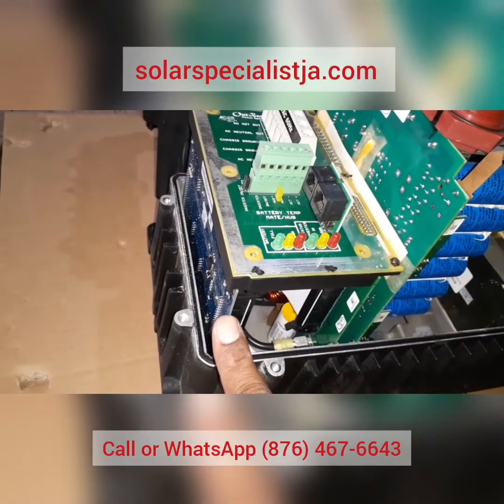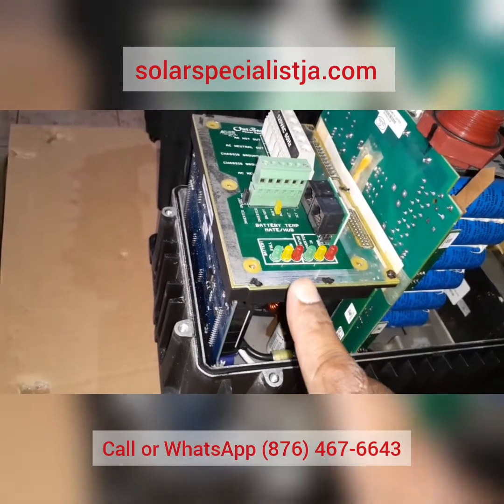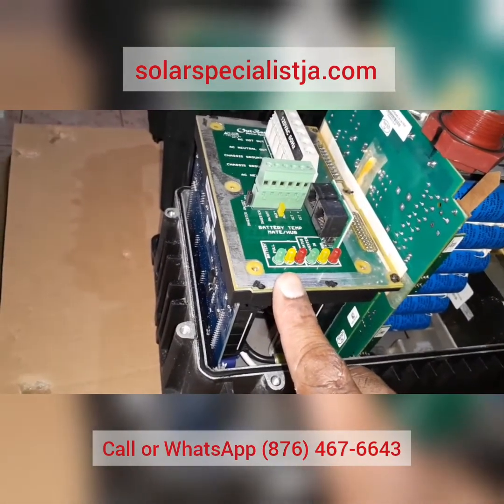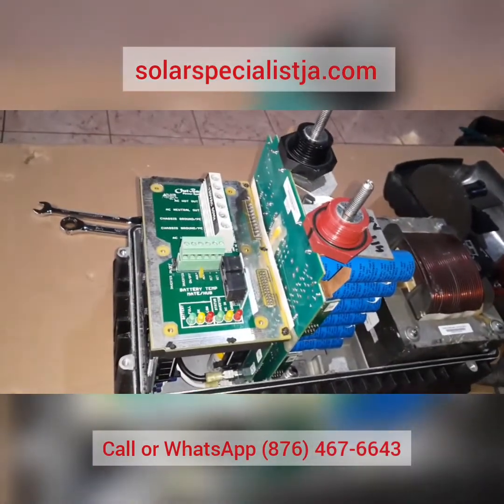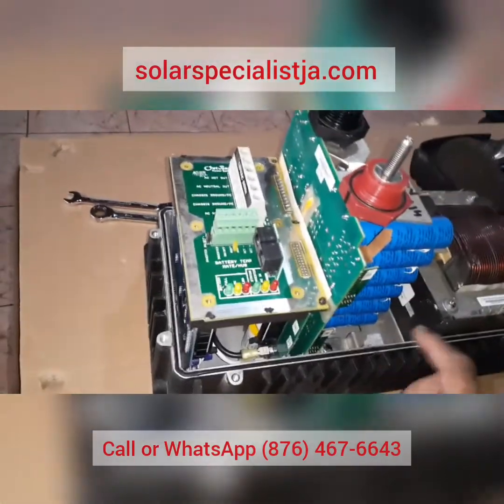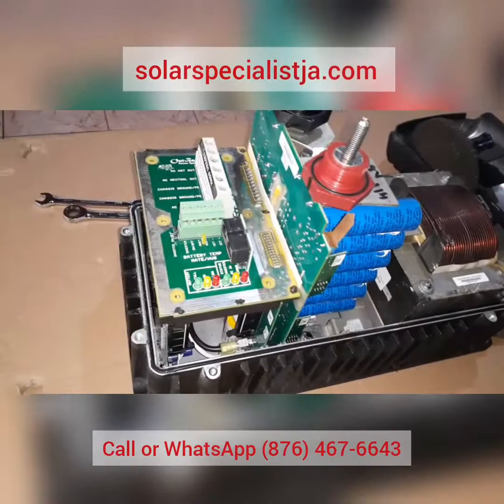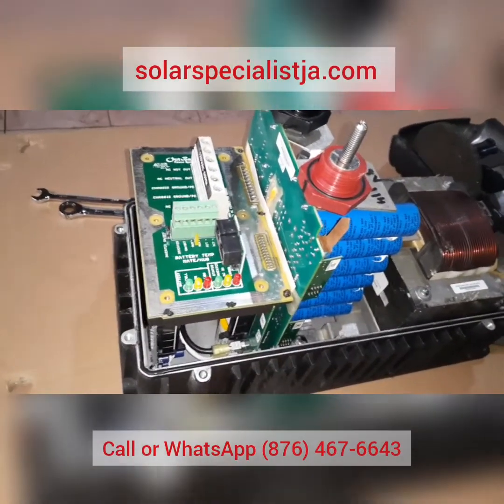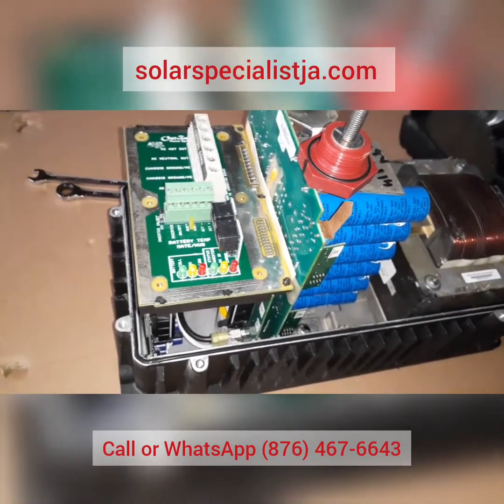Here's our control board that we'll be replacing today. These two boards are connected — this is our AC board — so you want to be careful when removing them. There are three gaskets that you want to remove: two O-ring gaskets right here, and another big gasket that goes right around the unit. You want to remove them so you don't get them lost, so that when you're reassembling the unit you'll know where to find them.